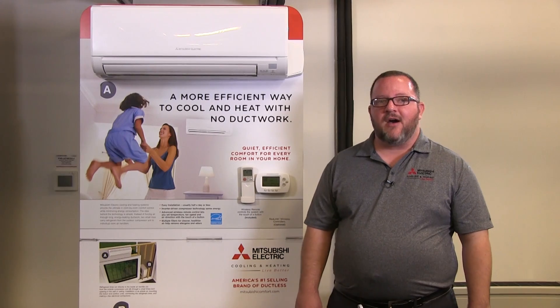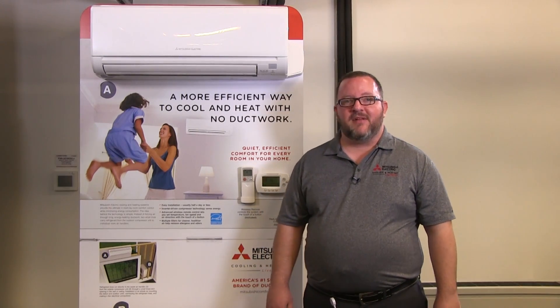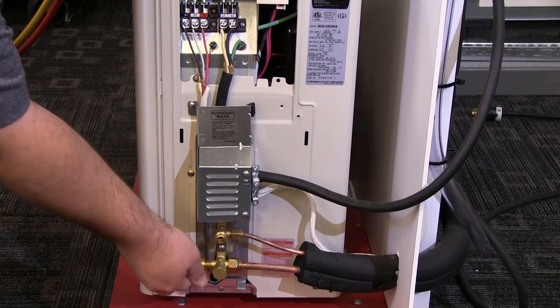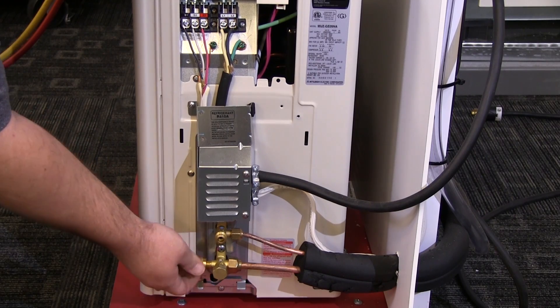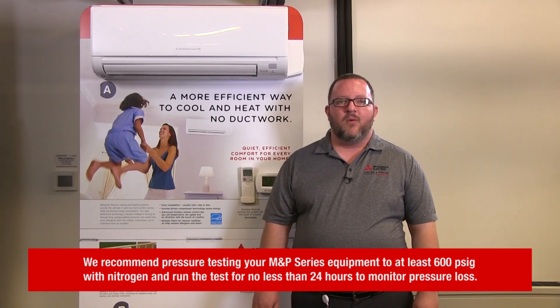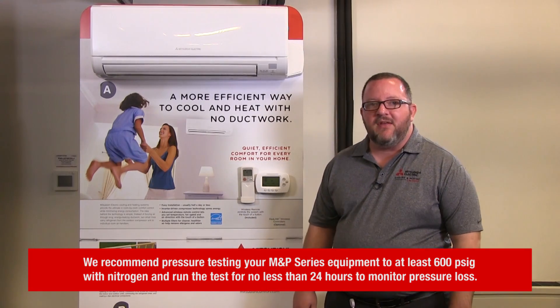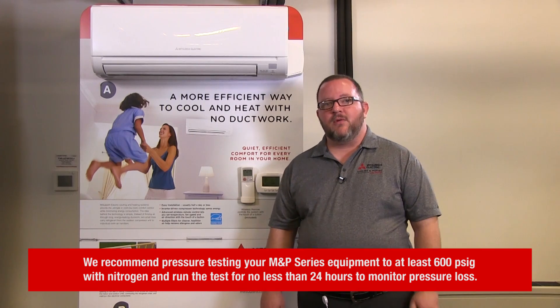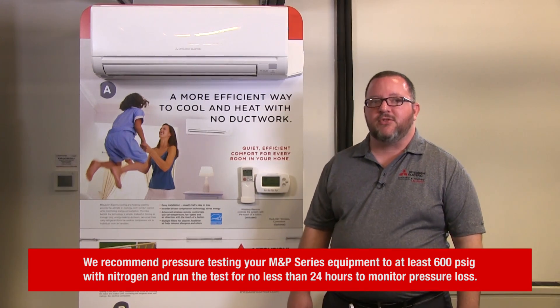You also want to make sure that you thoroughly insulate any exposed copper pipe to prevent condensation. Now that the system has been hooked up, it's time to pressure test the system. Currently the king valves are closed on both the liquid lines and suction lines, so we can use the service port attached to the suction king valve to pressure test the system. We recommend pressure testing your M&P Series equipment to at least 600 PSIG with nitrogen, and run the test for no less than 24 hours to monitor pressure loss.